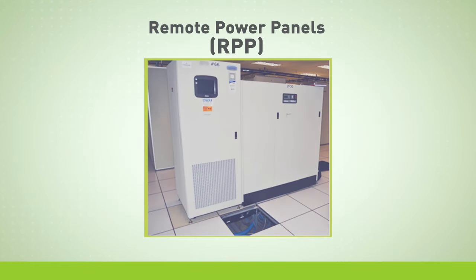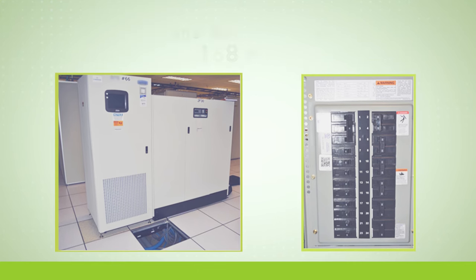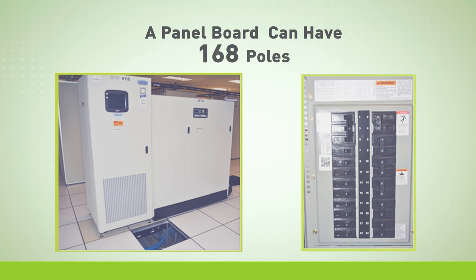Floor PDUs are connected to a series of remote power panels referred to as RPPs. These are larger versions of the breaker panel in your home. If you look at this panel, it has multiple points where you can connect wires to run to your equipment. These points are called poles. There are panel boards that can have 168 poles.